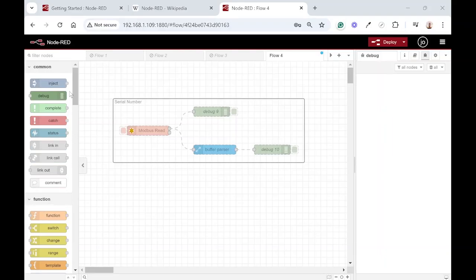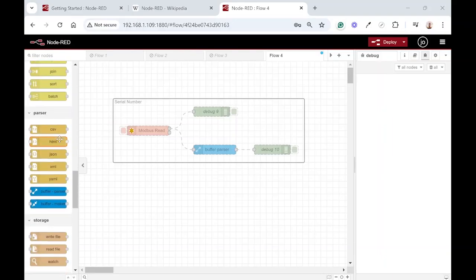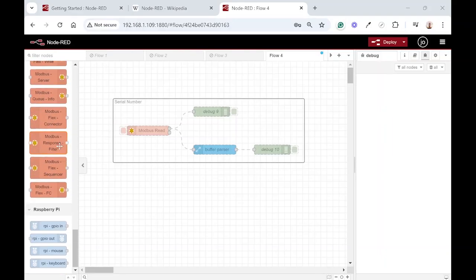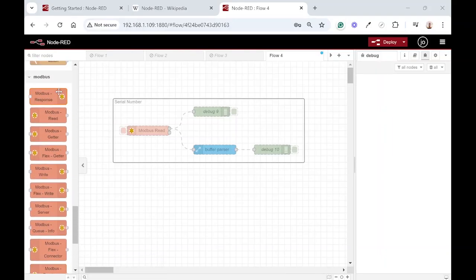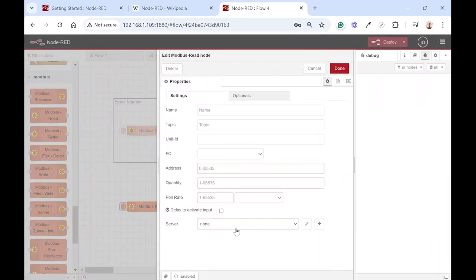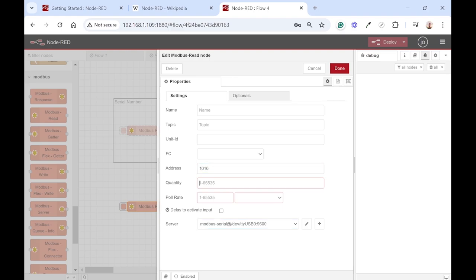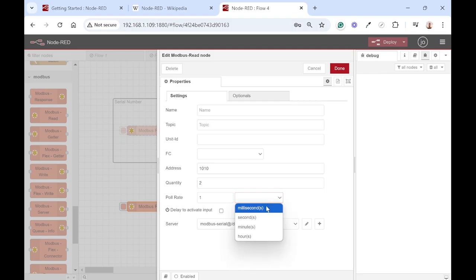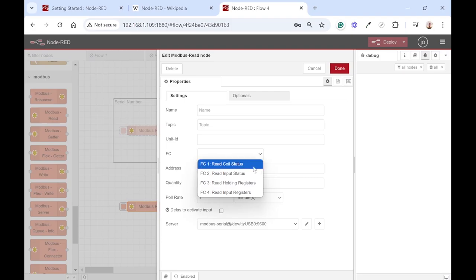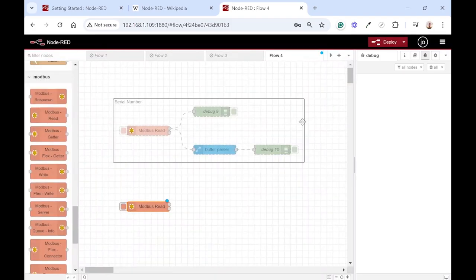Again we put in a Modbus read node and configure it. Use the same server, address is 1010, and we need to read two registers. Make it once every minute or so and the function code must be read holding register.